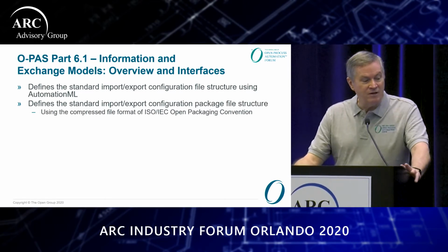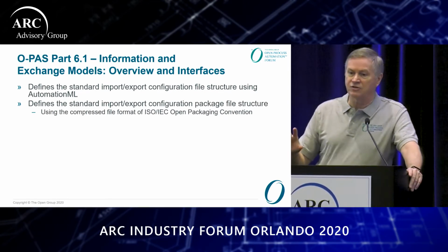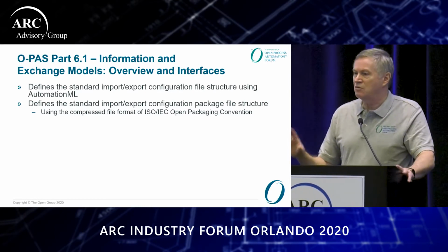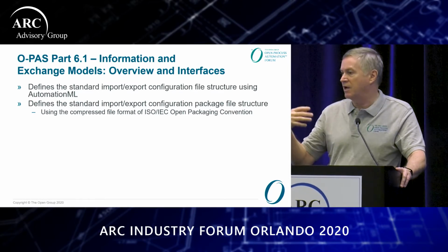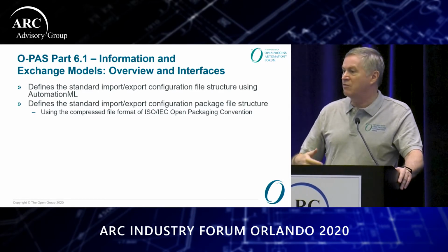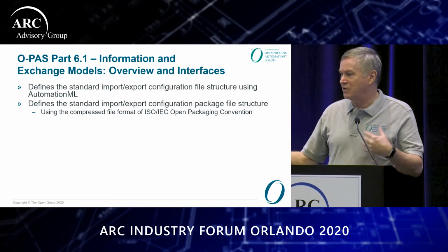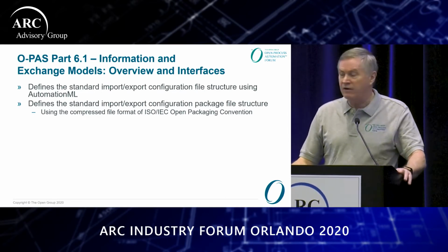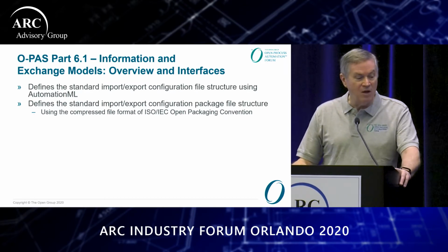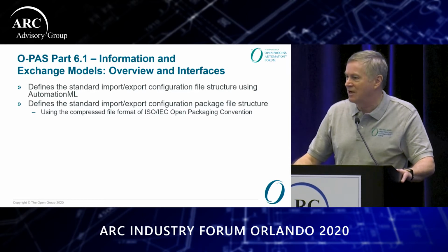We define a standard import package file structure. Okay, so it's not just one file for a project file. It actually contains multiple things. So you may have the source code from your 1131 program, along with the definition of your tags, along with the definition of 1499 and alarms, et cetera. And we use a compressed file format, which is based on the Open Packaging Convention. Basically, it's the same stuff that we use in the IT world.